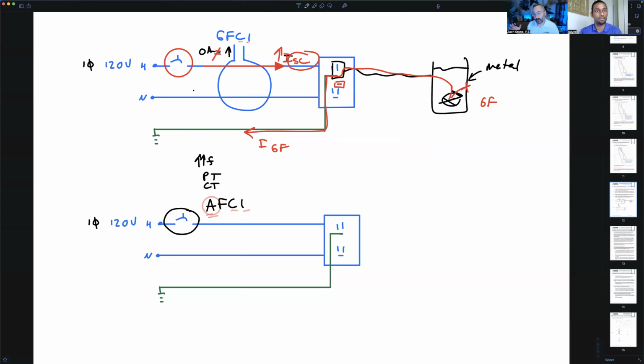dangerous arc. So they shouldn't be so sensitive that it's going to trip when you flick a light switch, or if I unplug my vacuum while it's running, where guaranteed there's going to be a little zap, a little arc in that receptacle. They shouldn't trip for safe levels of arcing. They're not supposed to. A big common complaint in the industry is that they do. Sometimes you get one when you install it and you just have to throw it out. It's way too sensitive. It trips all the time. But they're intended to just trip for dangerous levels of arcing, where a fire hazard could exist.